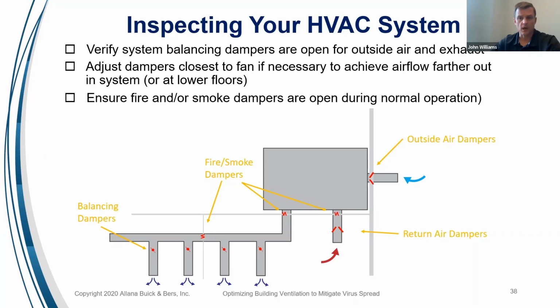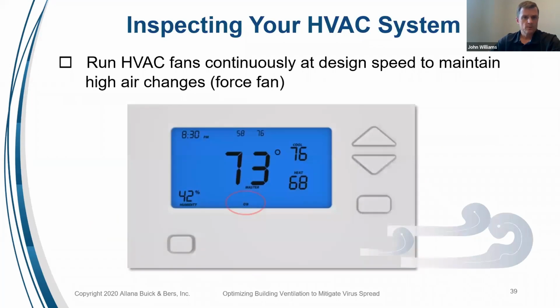One of the other things we find a lot when we're inspecting systems and units is balancing dampers. Often they get adjusted because somebody's hot, somebody's cold in an area. The damper is adjusted to try to get more airflow, less airflow, and the whole system is thrown out of calibration. But rarely are these ever set back to the original set points. Same thing with fire and smoke dampers. We're penetrating these firewalls in the buildings, and we have these fire and smoke dampers. It's not uncommon for us to find that these have dropped. We're pinching off the ductwork or completely closing it off, and we're losing airflow through the building. So it's important to check our fire smoke dampers to make sure that they're also open.